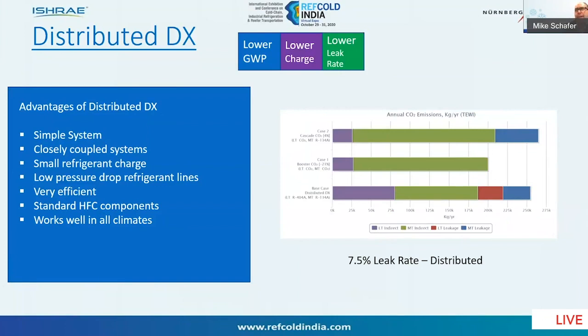And so looking at the TEWI calculation, comparing it to the booster and the cascade, you can see that the effect is more pronounced. In this case, we considered a 7.5% leak rate for the distributed systems, given that typically the line reductions are going to be at least half, and the system gas charge is going to be half of what you would see in a standard DX, as opposed to the 15% we looked at in the previous example.